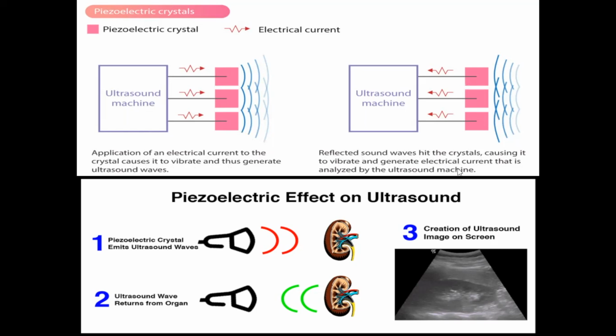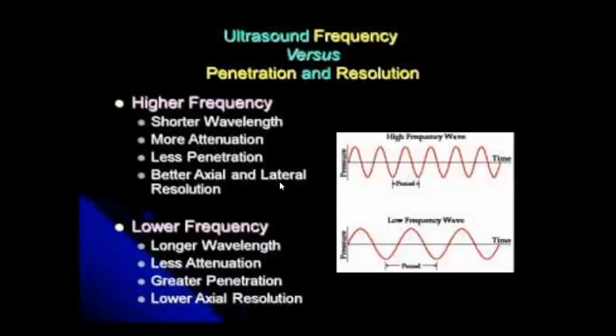So electrical current hits your piezoelectric crystals, causes ultrasound waves, and goes into the body. It reaches the organ and bounces back. The reflected wave comes back to reach the piezoelectric crystal. The piezoelectric crystal will again vibrate, converting the kinetic energy of your ultrasonic wave into an electrical signal, which goes through the cable to your ultrasound machine, the CPU, to create the image that we view on the screen.